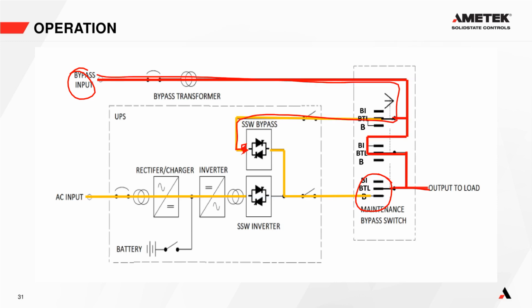That allows us to test the UPS without affecting the load circuits. So if we've done intrusive maintenance on the UPS, replaced the capacitors and all the control boards, we want to make sure when we power it back up that the static switches operate correctly. In the bypass to load position, we can switch bypass to load or inverter to load using the static switch and test those functions. We can even put a load bank on the output of the system, some resistive load on the output here.